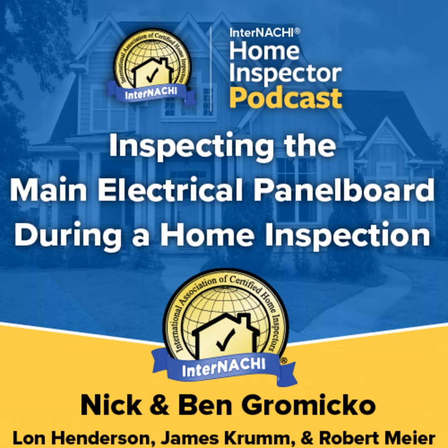There should be a circuit directory installed on the face of the panel board door, inside the panel door, or in a location adjacent to the panel door. The circuit labeling should be permanent and legible. Homeowners and contractors should use factory-made panel labeling kits. This requirement helps protect occupants and contractors from injury that could result from shutting off or turning on the wrong circuit breakers.